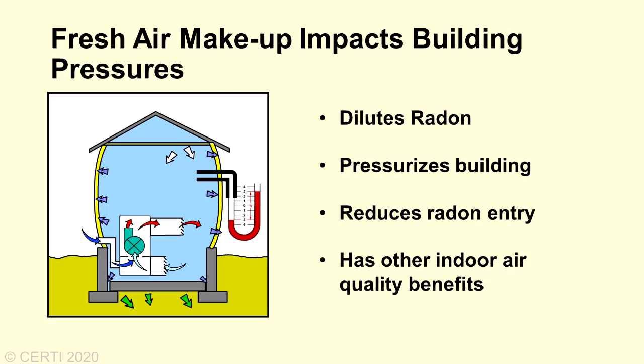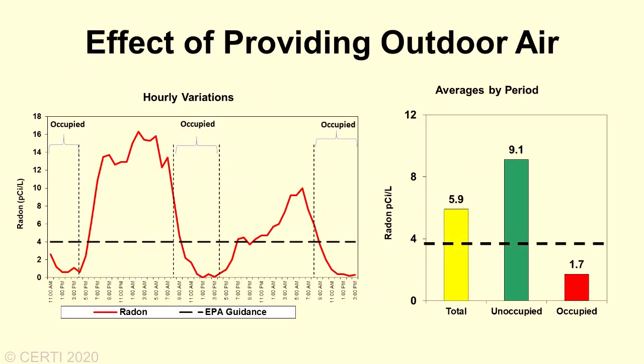Providing outdoor air can do two things. One, it will dilute radon. And two, it can also create a positive pressure inside the room or building that will resist the entry of radon. Here's an example of an hourly radon measurement taken in a school where fresh outdoor air was only provided during occupied hours. One can clearly see that radon levels were greatly reduced to below the EPA guidance of 4 picocuries per liter when the outdoor air was provided, even though the overall average for a typical test period of 2 days was above 4 picocuries per liter.